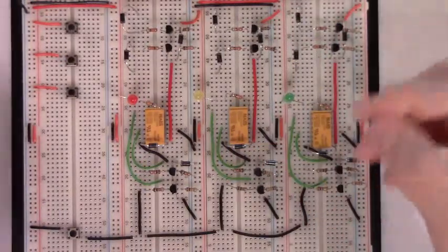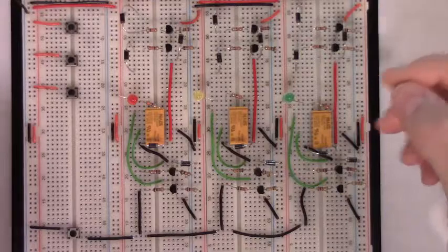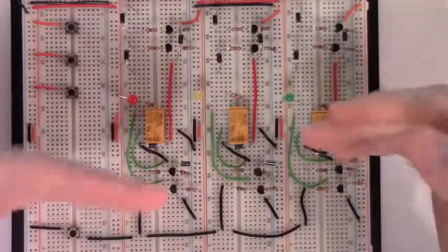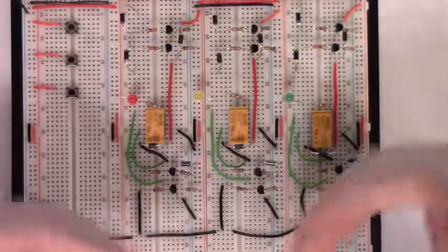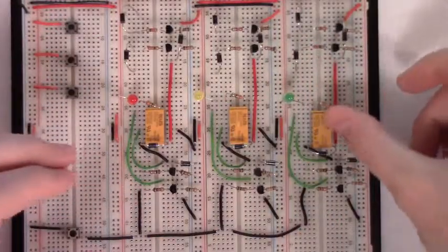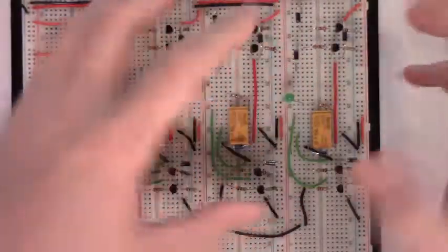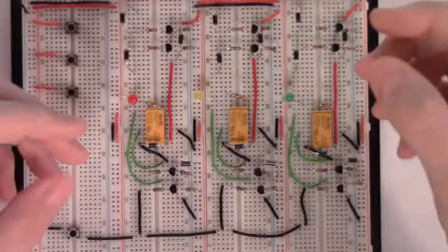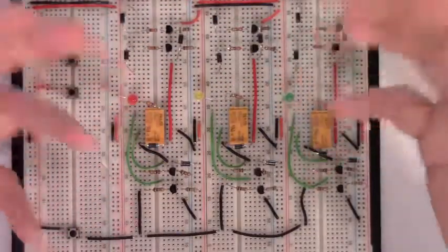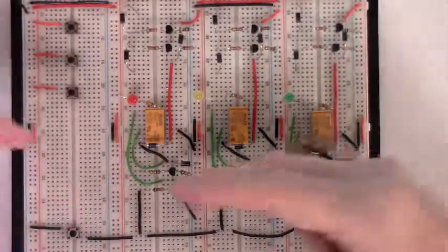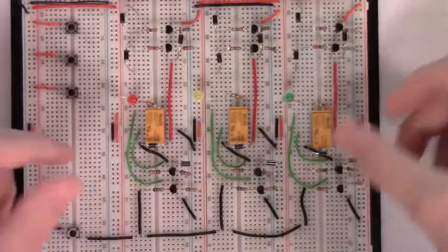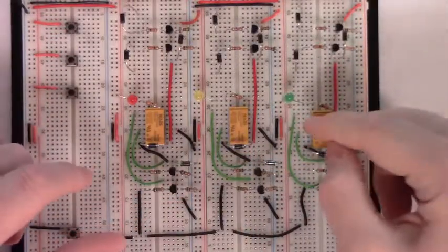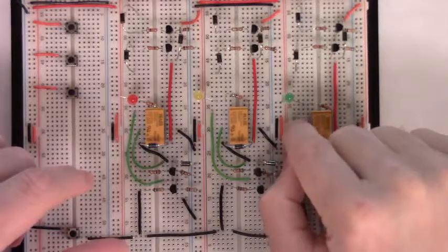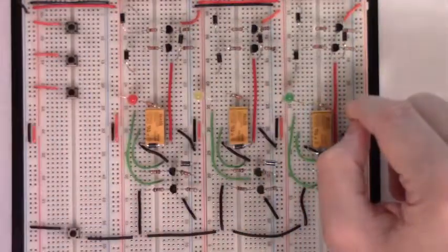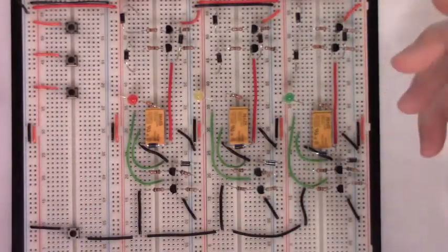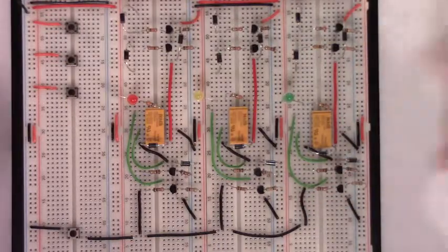In a circuit this size, that's one of the great things about walking through each step of it, and that's the reason you test each one. If we had continued on and I hadn't caught that, I'd have all those bird's nest control wires running over this, and then I'd have to wonder what's wrong. Well, doing this test one at a time as we go helped me at least capture this wiring problem before we moved forward. But at this point, we can move forward. Let's look back at the schematic.